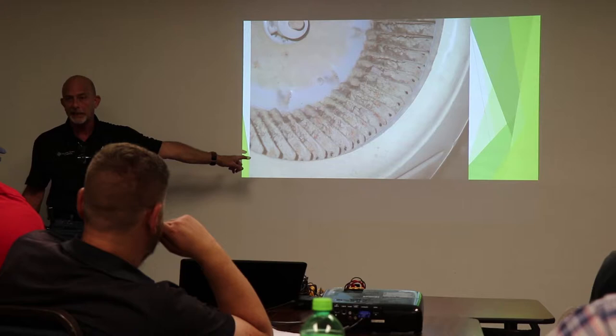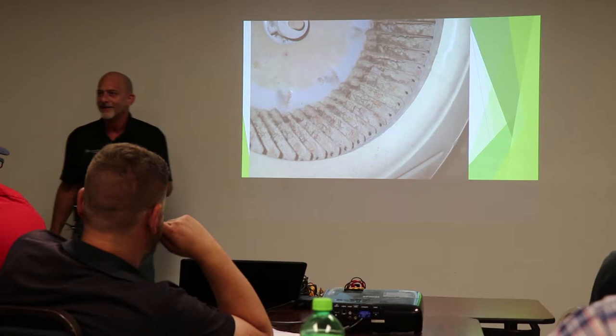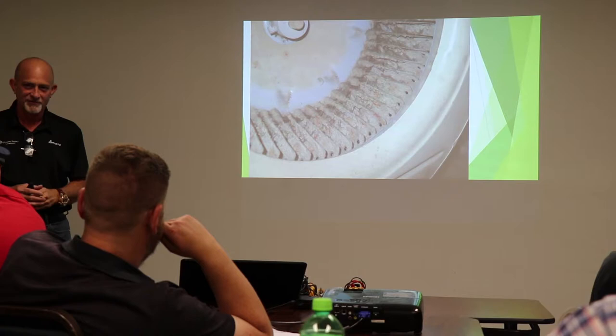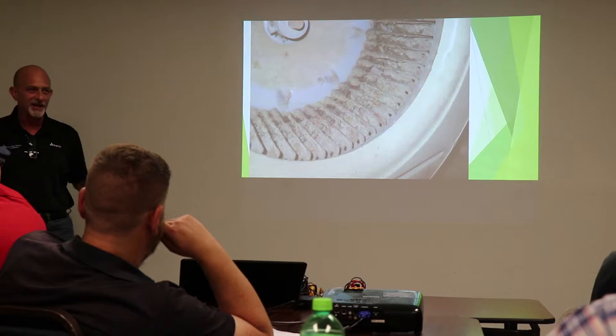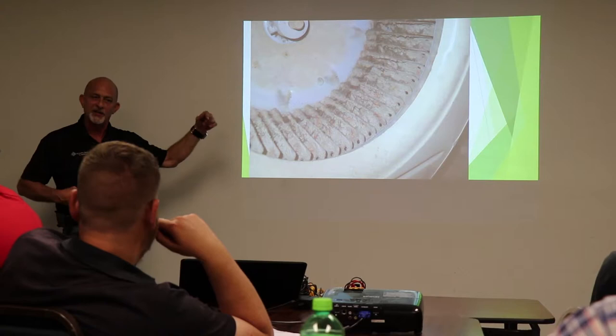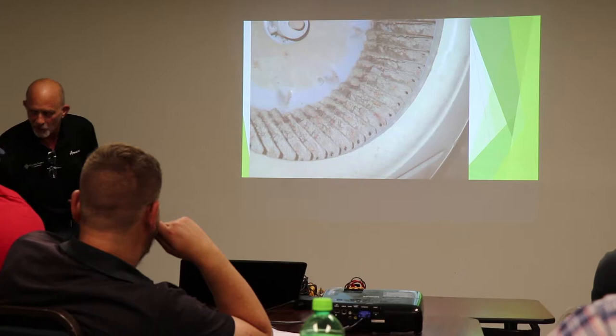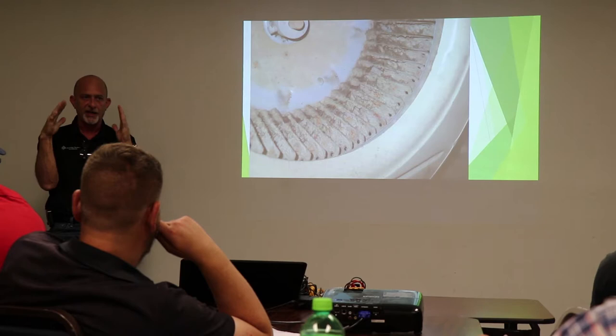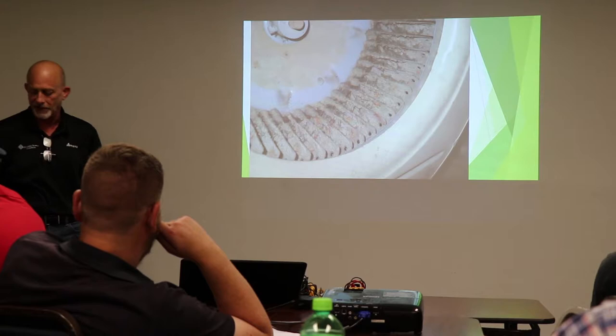Now, be careful, guys, because somewhere in all of that, there's a weight. So a little balance. If you knock the weight off, what happens? You got to replace the wheel. So be careful. Don't knock weights off. Usually what happens to them, if you catch it in time, you're fine. If you don't, and we're all plugged up, the wheels implode. Everybody's ever seen them implode? The sides suck in, and then they go up to a point. And you hear it, and they take out the housing and everything else. And you got to replace the whole thing.